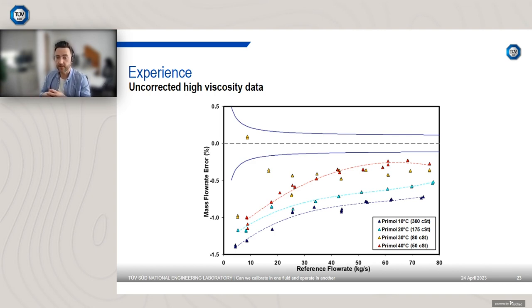Changing to the high viscosity data, in this case this is the trade name for the fluid, and it's called Primol. We have 10, 20, 30 and 40 degrees Celsius data once again. But because it's a medium to high viscosity fluid, by altering the temperature we alter the viscosity. So we're now operating at 50, 80, 175 and 300 centistoke. You can see that there appears to be a clear underreading. However, a bit of scatter. It's not the nicest data to try and put a trend line through. We've got different polynomials for each individual temperature, and a couple of what look like rogue points for the 30 degrees Celsius data. Again, likely to be the zero effect.